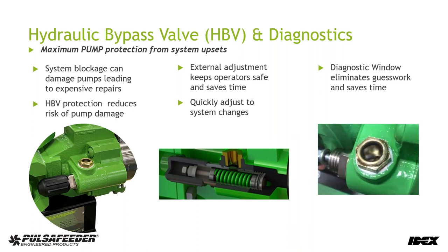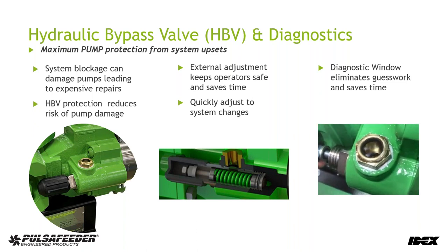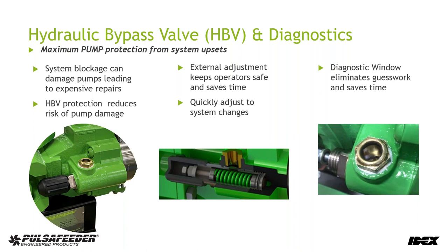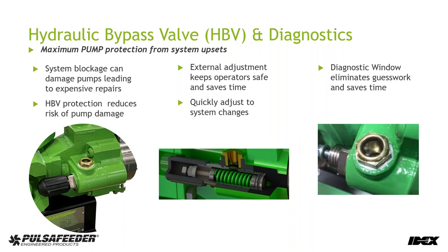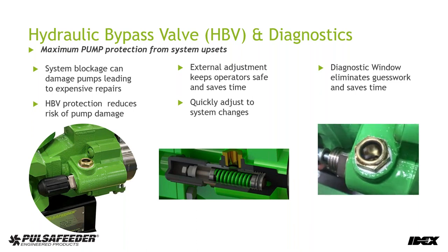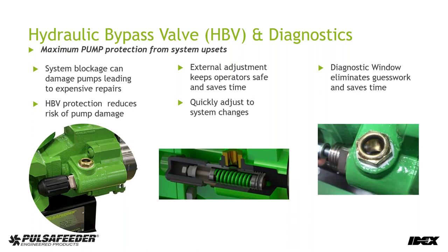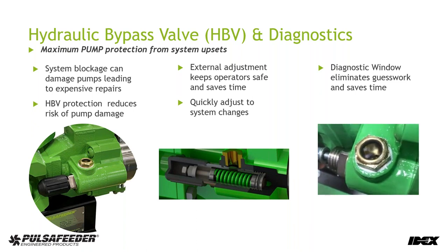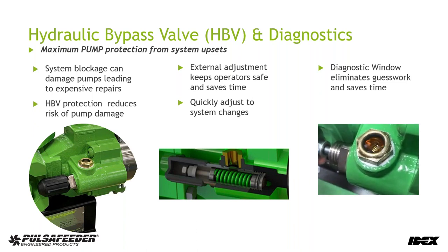You can see the video in there that's operating. Also, normally when you walk up to the pump, we've had some of our field personnel and actually some of our customers say that this is one of the most unique and innovative features on the market. Not many other pump manufacturers have this, but this gives you insight into your pump operation. Under normal operating conditions with this properly set, as you can see in that little video clip there, there's no oil present until it goes into upset condition.